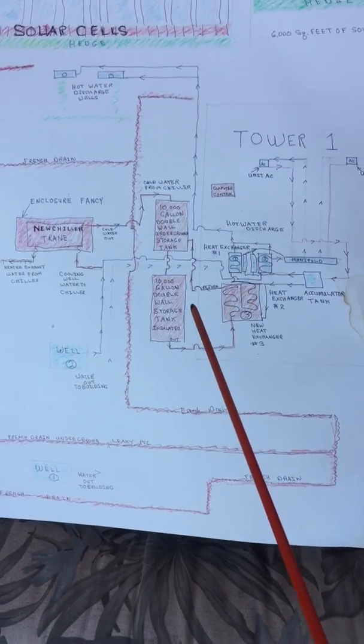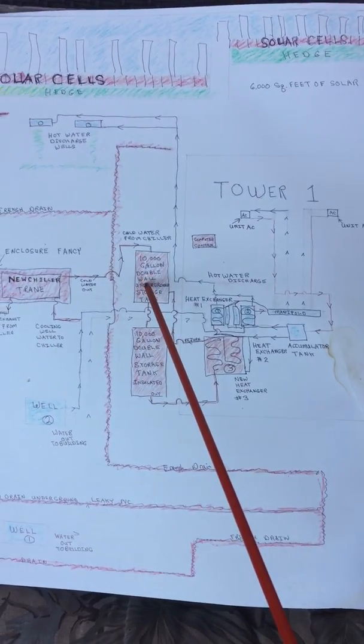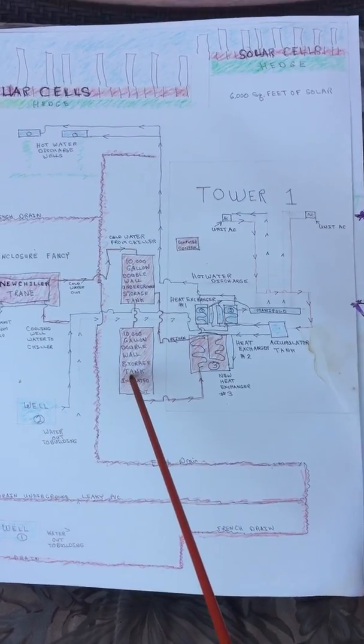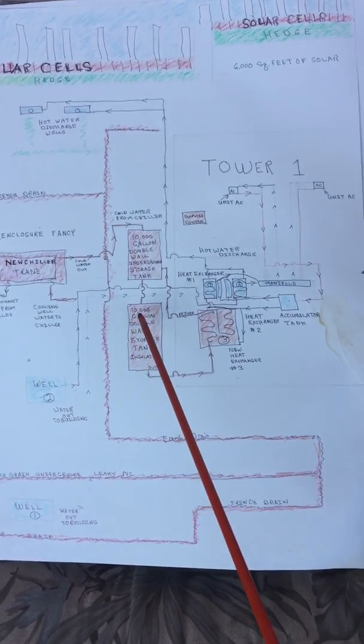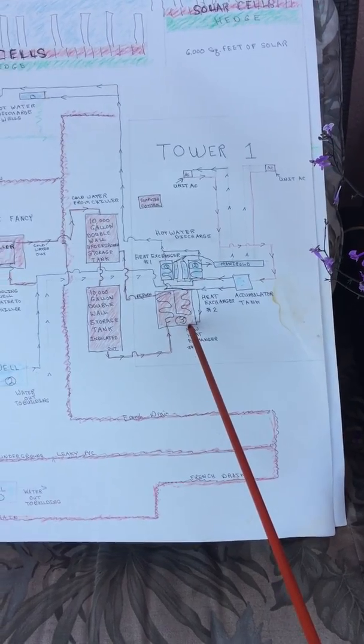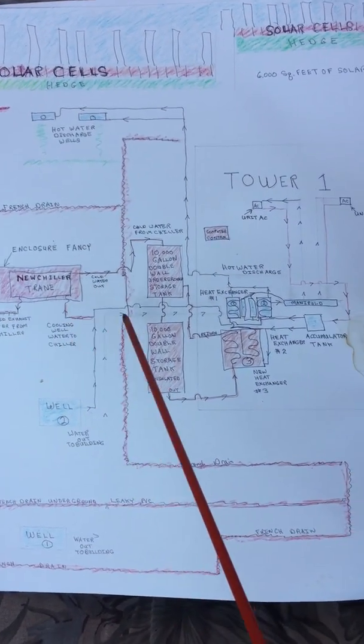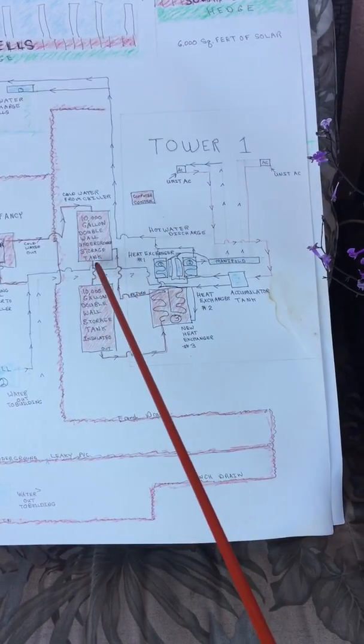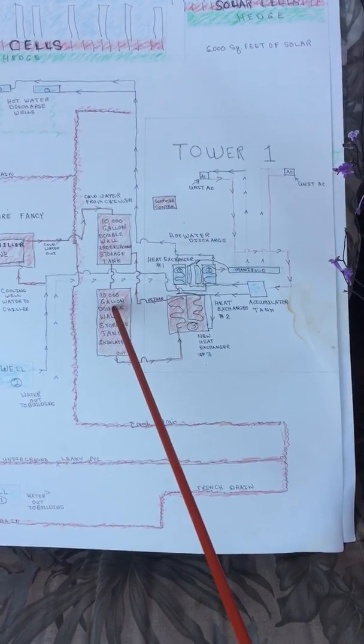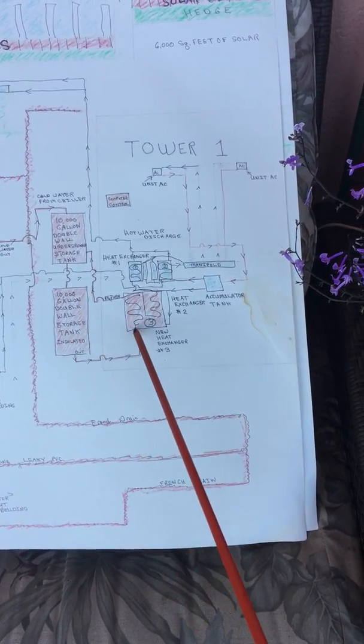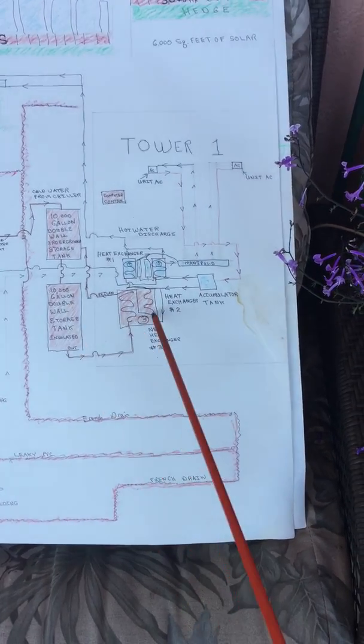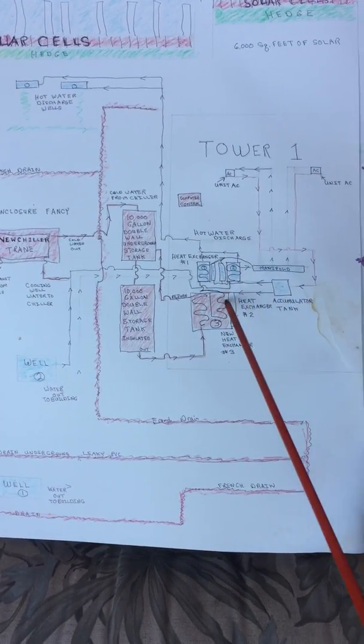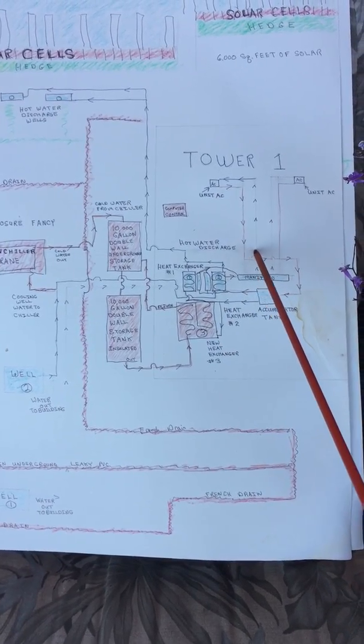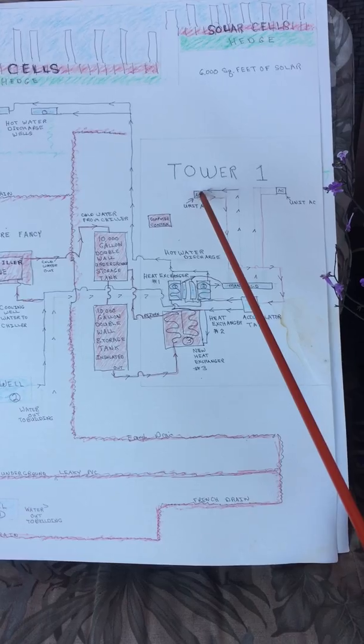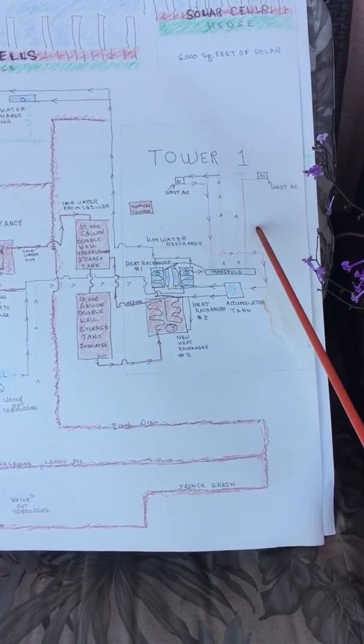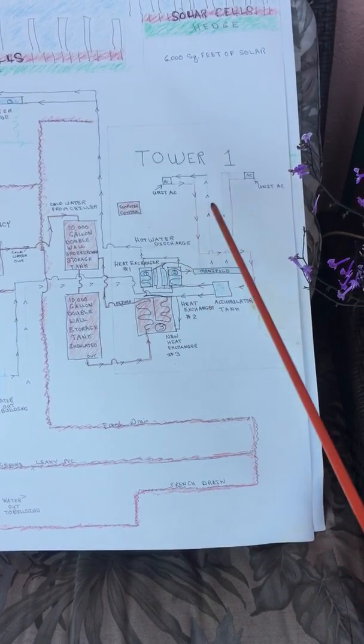So my idea is to install 2 10,000-gallon insulated double wall storage tanks underground, nobody will see them, and a new heat exchanger number 3, and a chiller system. Now we fill up these storage tanks with water that's between 45 and 65 degrees, and during the day this heat exchanger, because this water is nice and cold, will easily cool the whole building. This water is pumped up into the units, goes through the AC in the unit, comes back down, and it's recycled, but it gets hot.